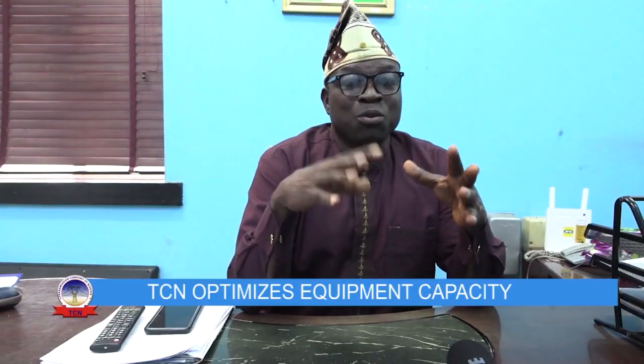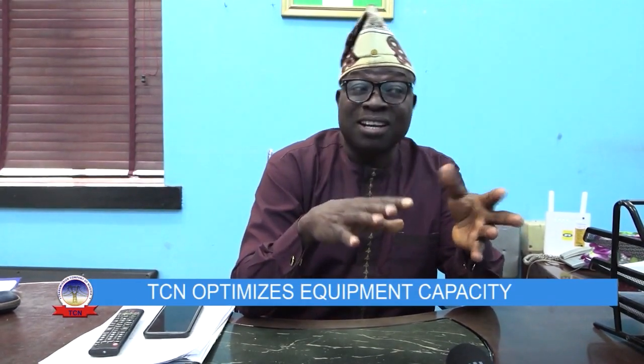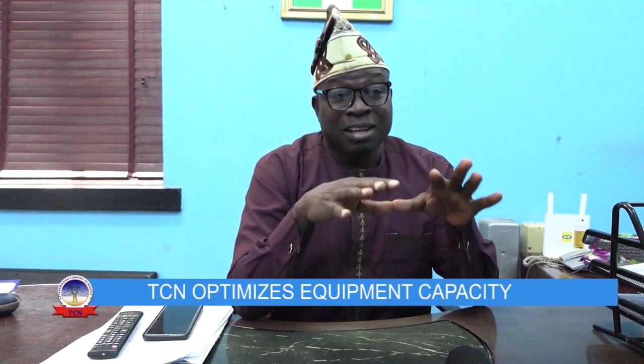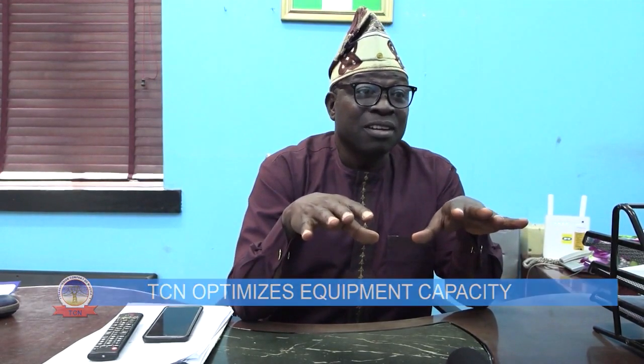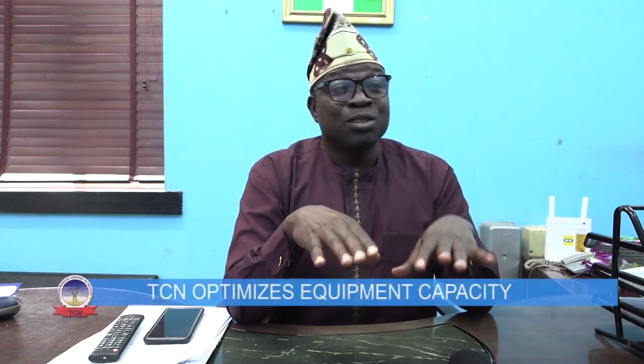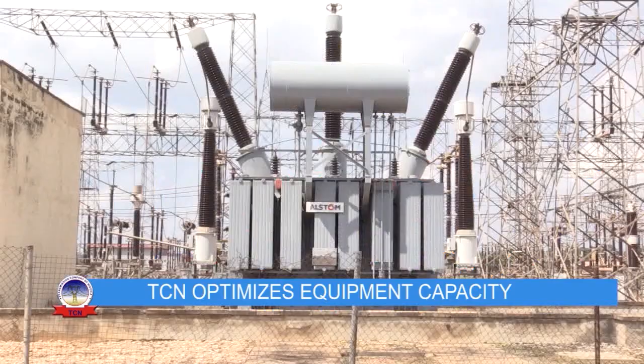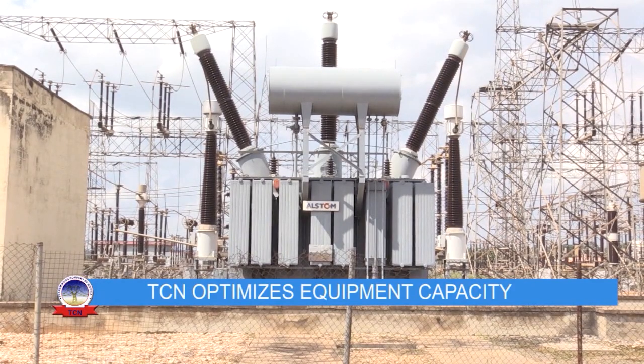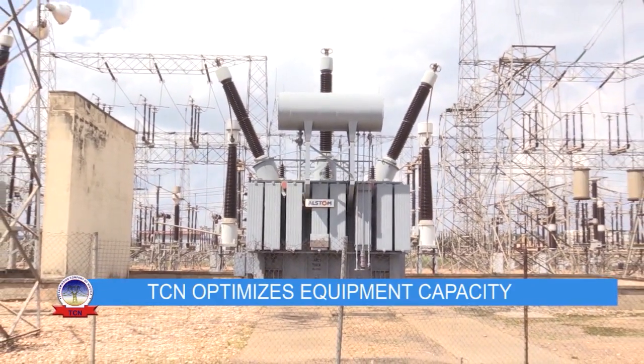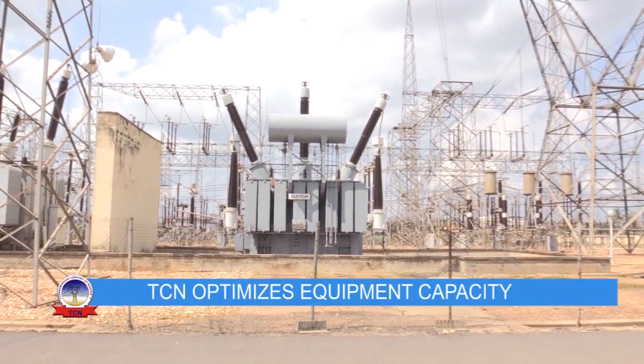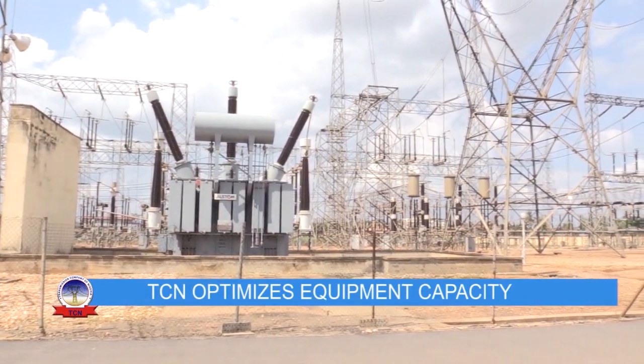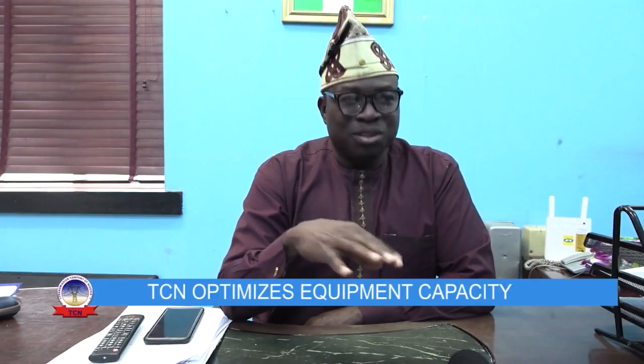byproducts. When this deterioration happens, you have water and oxidation byproducts getting created inside the oil. In fact, engineers will say the oil is getting cracked. You're going to have sludges in the transformer oil. So we have to do something to bring back that oil to the former state it was in when it was brand new. So we attempt to bring back the oil to a very good state as it was when it was new. That is what regeneration does.